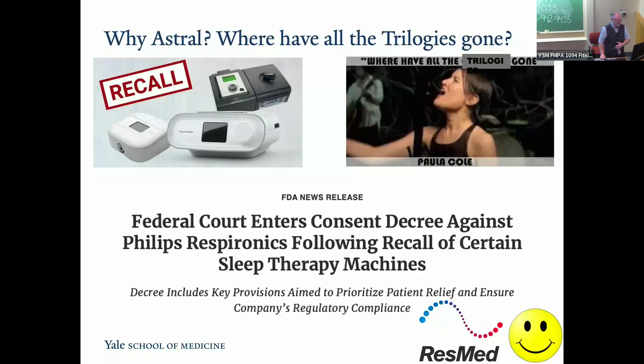So ResMed, we are all familiar with AVAPs, but ResMed talks about IVAPs. And what is that? So IVAP stands for Intelligent Volume Assured Pressure Support. It doesn't target the tidal volume. So when we have our V60s, or pressure regulated volume control in the AVEA, I forget what the acronym is now for PRVC, or the trilogies, we're familiar with VAPs where we set a target tidal volume, we set a pressure support min and max range, and the machine figures it out.